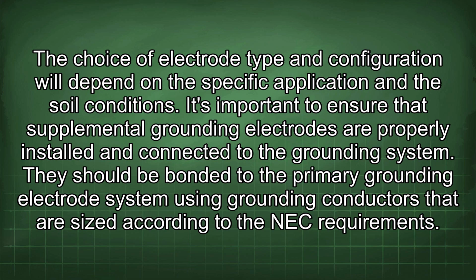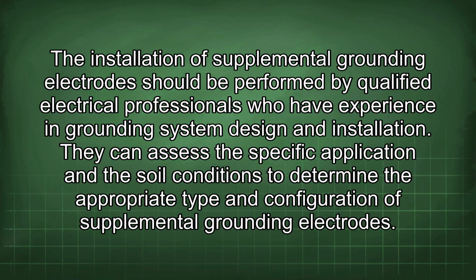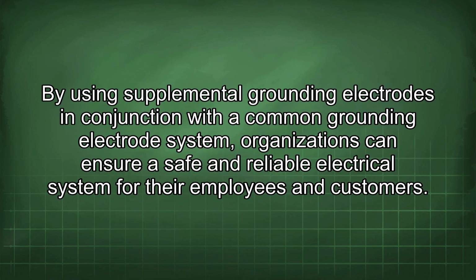It's important to ensure that supplemental grounding electrodes are properly installed and connected to the grounding system. They should be bonded to the primary grounding electrode system using grounding conductors that are sized according to the NEC requirements. The installation of supplemental grounding electrodes should be performed by qualified electrical professionals who have experience in grounding system design and installation. They can assess the specific application and the soil conditions to determine the appropriate type and configuration of supplemental grounding electrodes. By using supplemental grounding electrodes in conjunction with the common grounding electrode system, organizations can ensure a safe and reliable electrical system for their employees and customers.